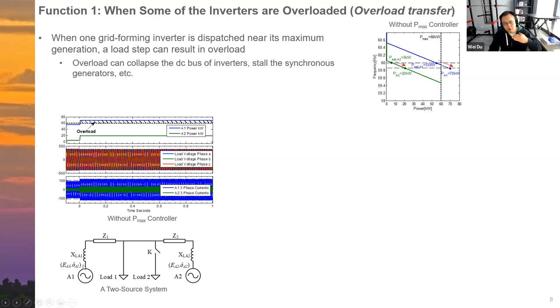They keep their internal voltage constant during the transient, so their currents come up very autonomously to meet this load change. However, there are some problems for this situation because A1 is already close to its maximum before the fault. Before the disturbance. Then we can see that after the disturbance, the grid forming inverter output power for A1 exceeds its maximum. So this does cause overload of A1.